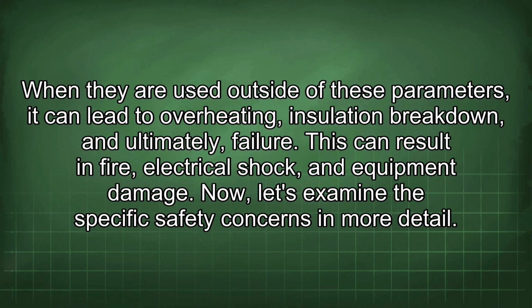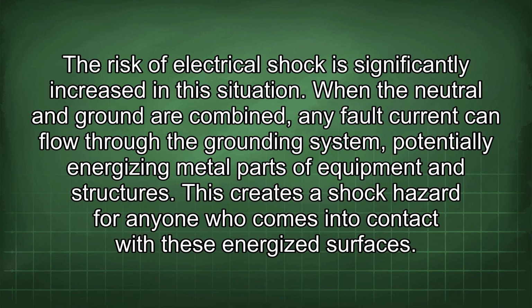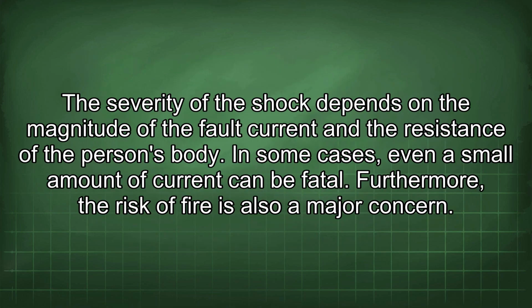Now let's examine the specific safety concerns in more detail. The risk of electrical shock is significantly increased in this situation. When the neutral and ground are combined, any fault current can flow through the grounding system, potentially energizing metal parts of equipment and structures. This creates a shock hazard for anyone who comes into contact with these energized surfaces. The severity of the shock depends on the magnitude of the fault current and the resistance of the person's body. In some cases, even a small amount of current can be fatal.